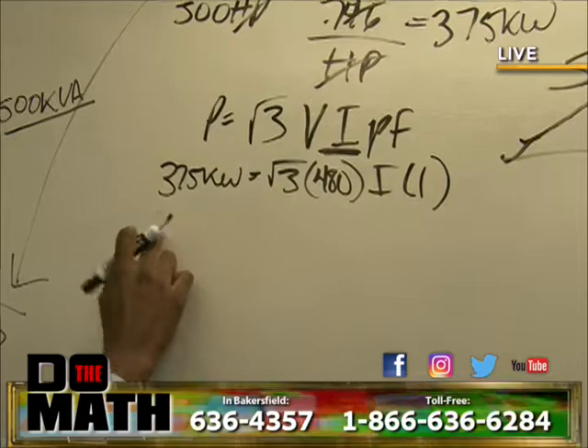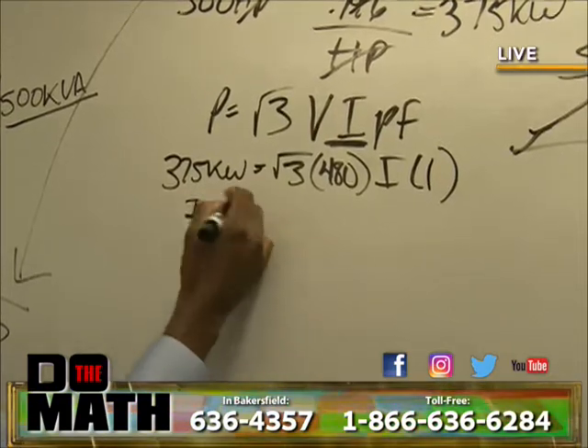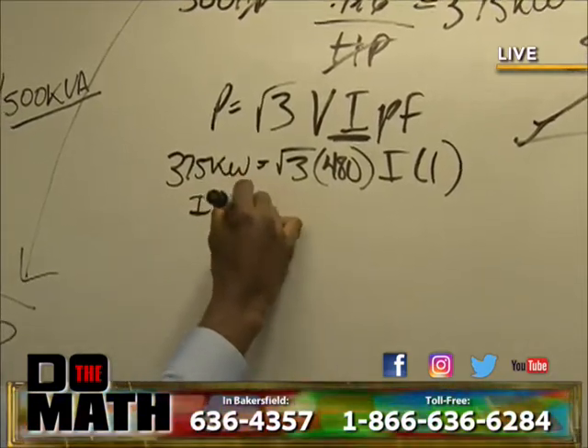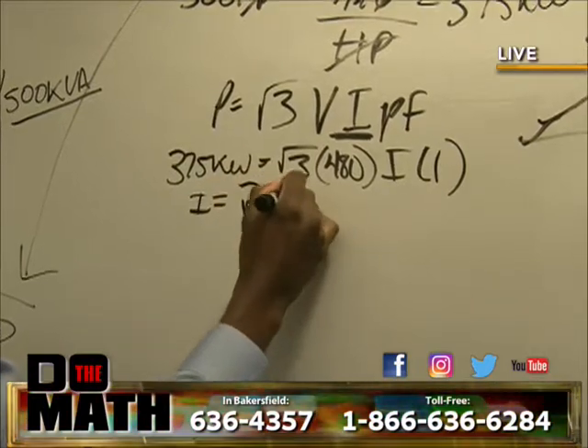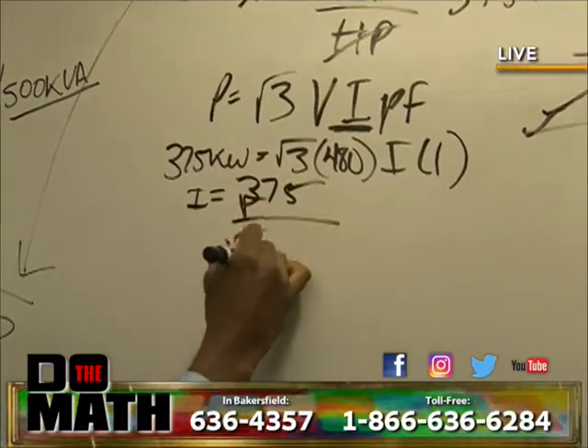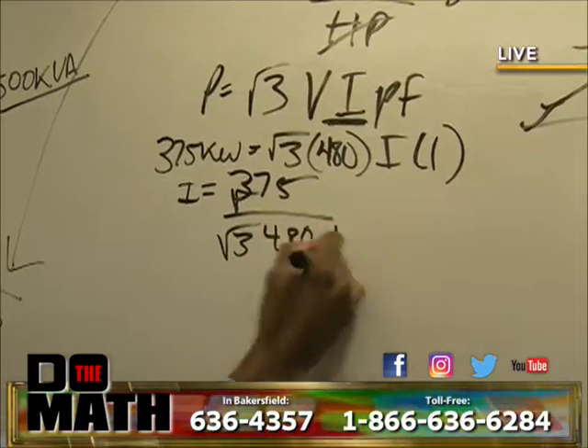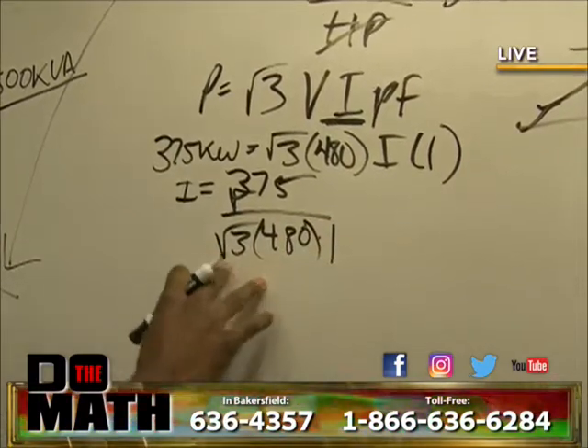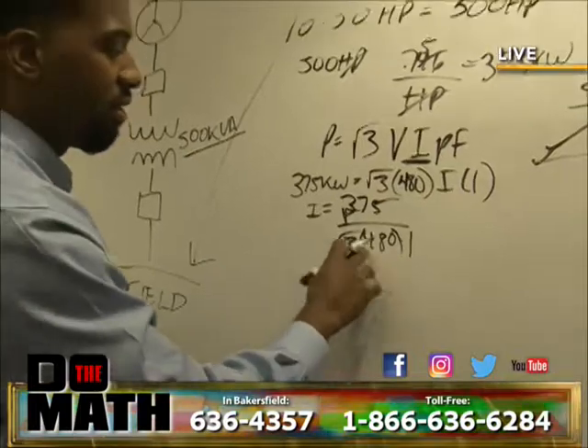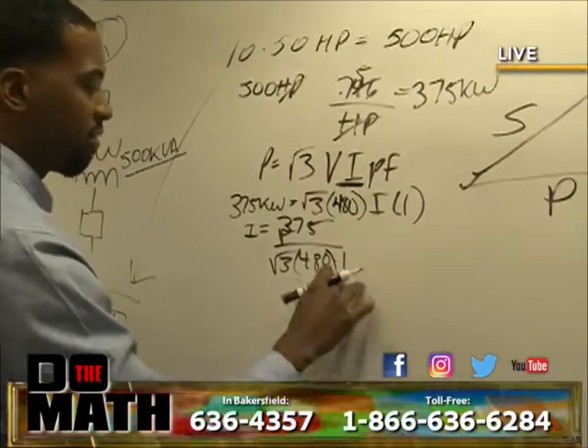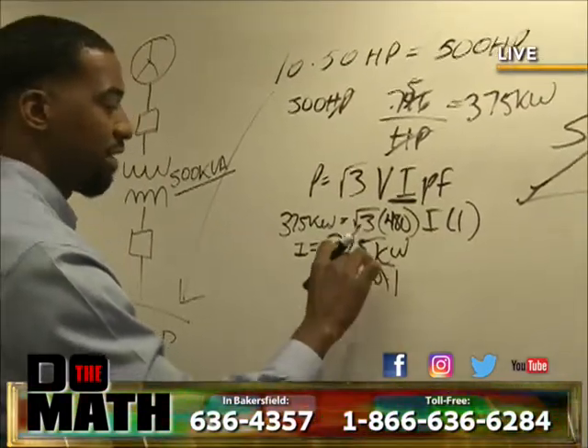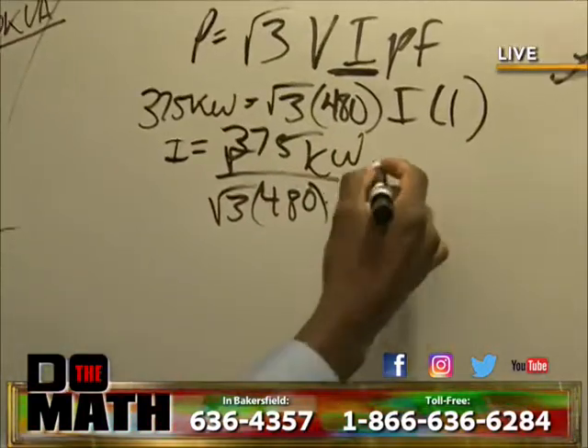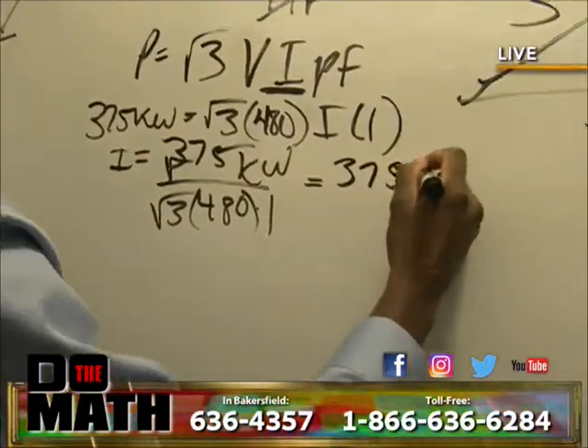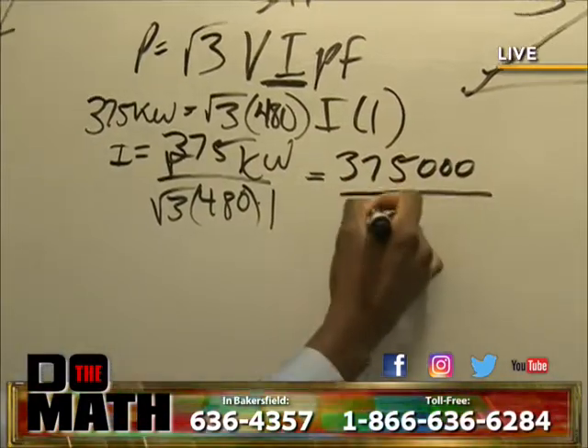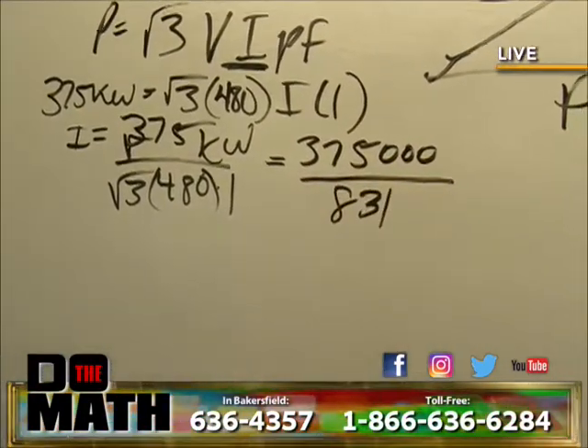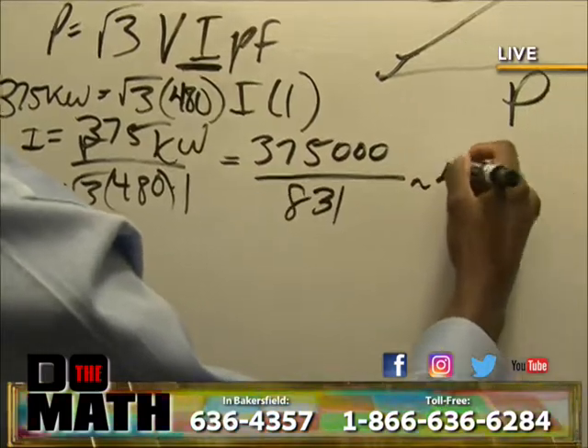So now we solve for I. I is equal to 375 divided by square root of 3 times 480 times 1. I work with these factors all the time, so square root of 3, 1.732, times 480 is 831. And remember this is kilowatts, so we have the prefix kilo, so you multiply by 1,000. So 375,000 divided by 831.